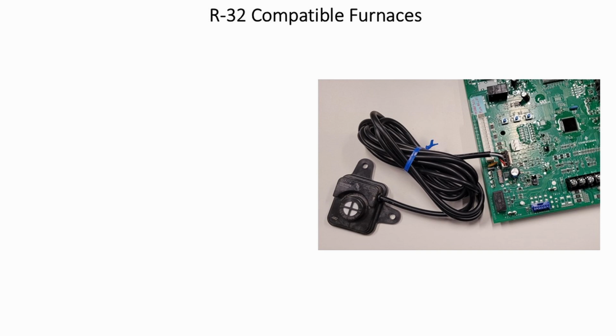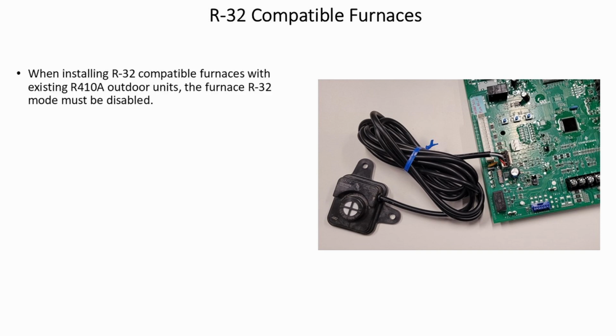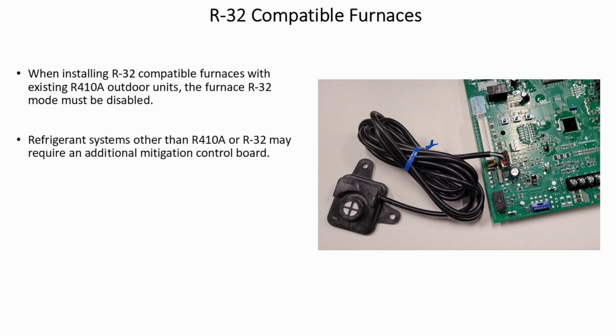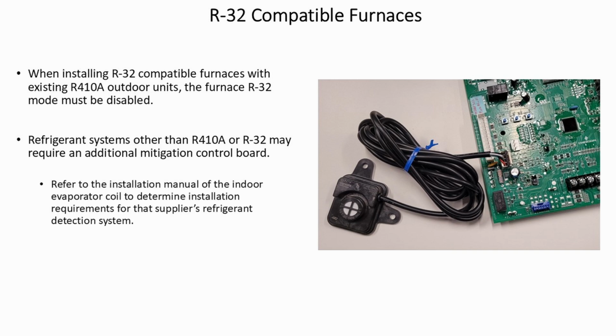R32 compatible furnaces. When installing R32 compatible furnaces with existing R410A outdoor units, the furnace R32 mode must be disabled. Refrigerant systems other than R410A or R32 may require an additional mitigation control board. Refer to the installation manual of the indoor evaporator coil to determine installation requirements for that supplier's refrigerant detection system.